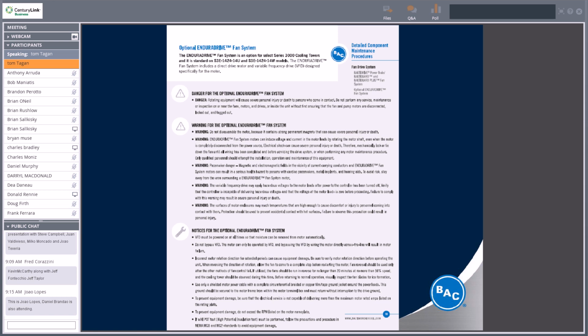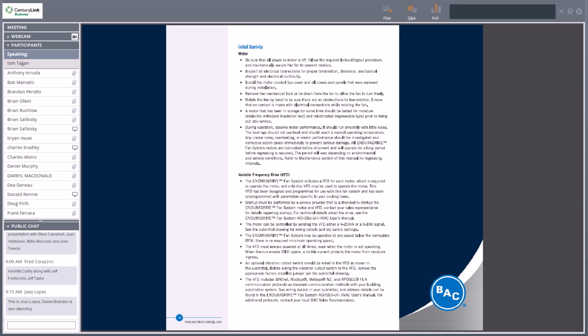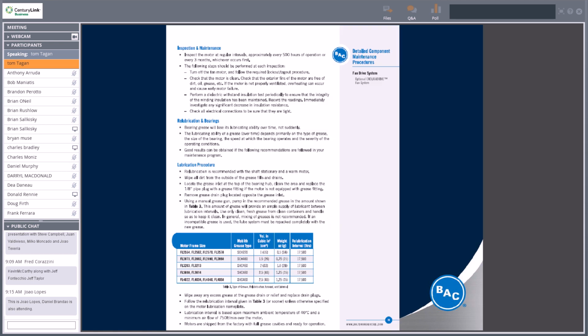BAC has introduced a direct drive motor. It's a Baldor motor with direct drive, so there's no gear and no belt. The motor directly drives your fan. It is only available on this series cooling tower, and I believe right now 25 horsepower and above. But this has been an option that facilities people have been asking for years, and it's been an option that cooling tower manufacturers have been talking about for years, but it is now available on the BAC cooling tower for this particular unit. And again, it's giving you the same recommendations on how to start it up and how to check to make sure that this type of drive system is operating properly.